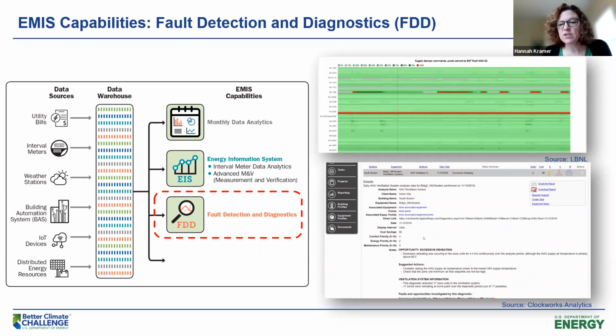This bottom chart shows some suggested actions for excessive reheat. Honestly, no one has time to sit there and look through their trend data, real time or retroactively, to find these issues, though if someone did, they'd find tons of stuff. So the FDD system is finding it for you, but the trick is you've got to fix it. That's always an issue: if you have a lot of problems, do you have the staff available to fix them?